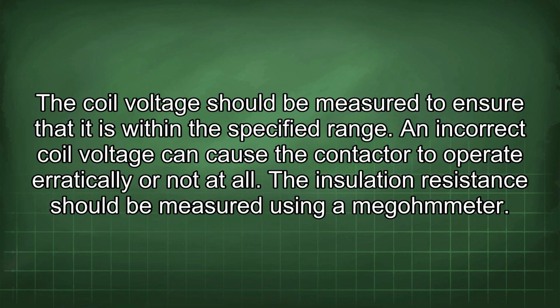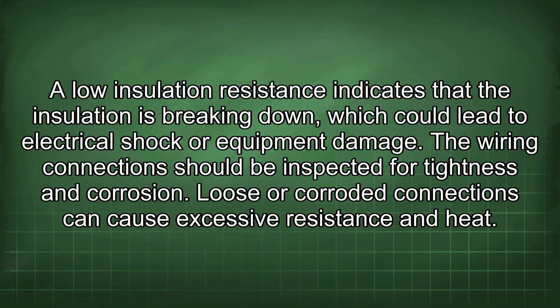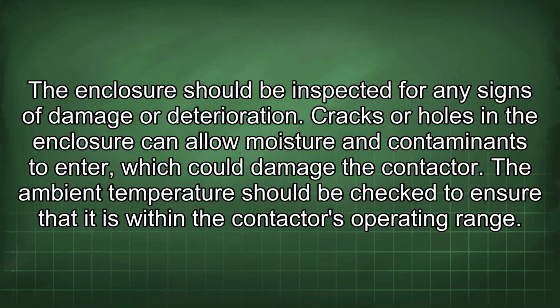The coil voltage should be measured to ensure that it is within the specified range. An incorrect coil voltage can cause the contactor to operate erratically or not at all. The insulation resistance should be measured using a megohmmeter. A low insulation resistance indicates that the insulation is breaking down, which could lead to electrical shock or equipment damage. The wiring connections should be inspected for tightness and corrosion. Loose or corroded connections can cause excessive resistance and heat. The enclosure should be inspected for any signs of damage or deterioration. Cracks or holes in the enclosure can allow moisture and contaminants to enter, which could damage the contactor.